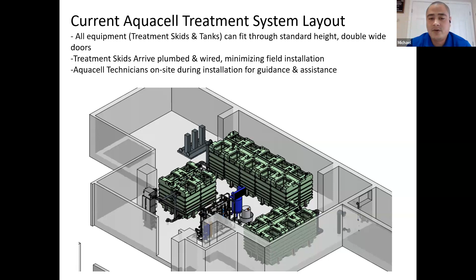Now touching on the operational challenges. The first one we want to touch on is makeup water control. Originally we designed an automated control system with an electronic valve that worked off a level switch. If the level switch in the treated water tank, which supplies the building, dropped below a certain level, the automated valve would open and water would fill the treated water tank.